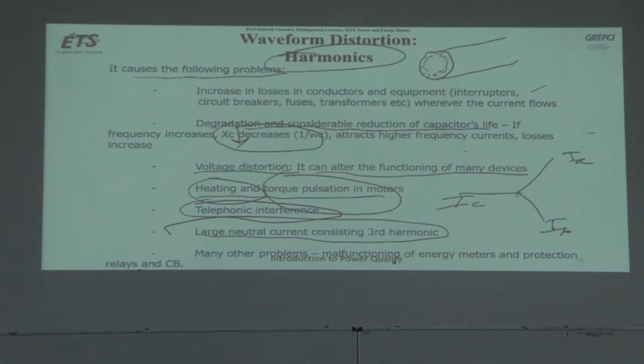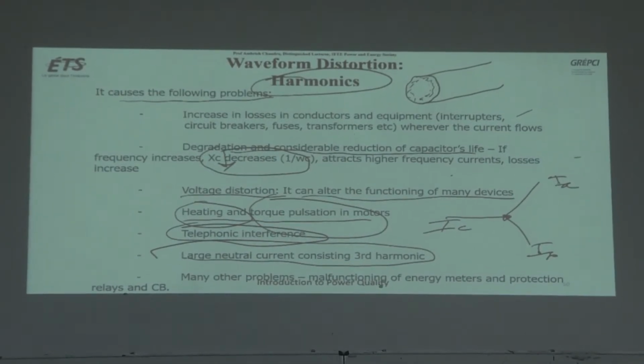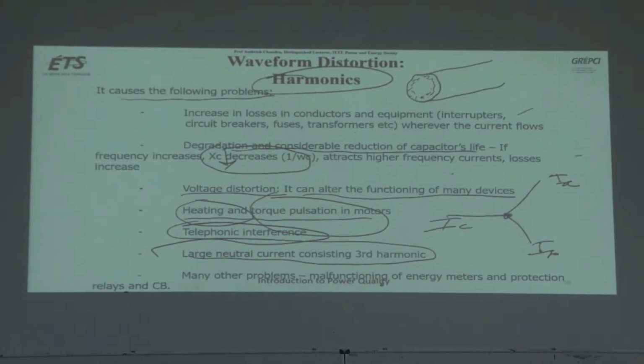So in ideal condition, the sum of 3 currents should be 0. But if you have the harmonics, the third harmonic is a zero sequence harmonic, IA0, IB0, IC0. They are in the same phase, so they will not cancel out. The sum of the zero sequence harmonic is not 0, it is the sum. Basically, it will increase.